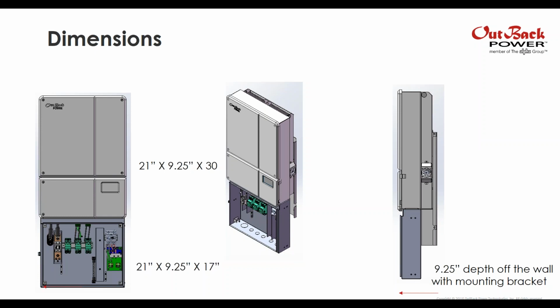But one of the things that we do is we put this knockout over here in the back upper top of SkyBox. See if I can bring up a laser pointer. That work? Yeah, it looks like it's working. And then that supports 3/4 inch conduit. So you'd slide a little stub of something that's 3 feet, 5 feet long of 3/4 inch conduit through there. And then that provides a good lifting point, a good handle for two people to put SkyBox up on the wall. Turn off the spotlight.